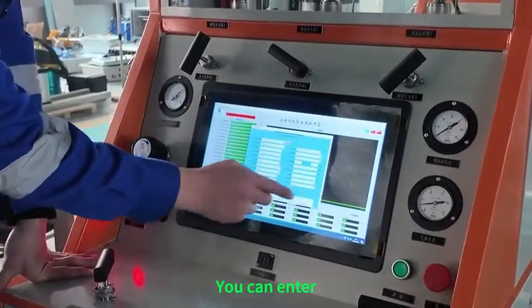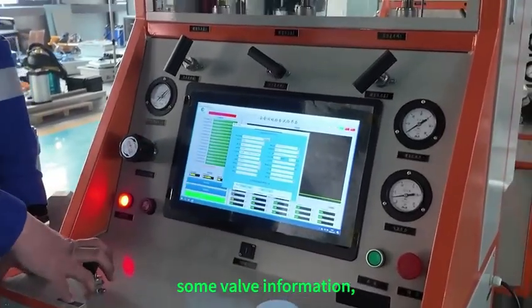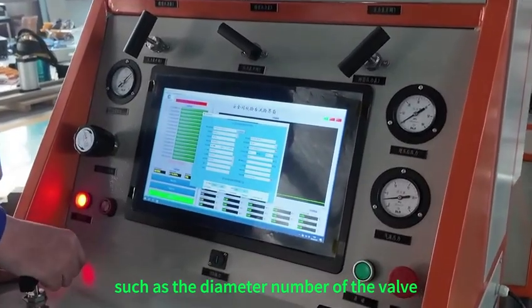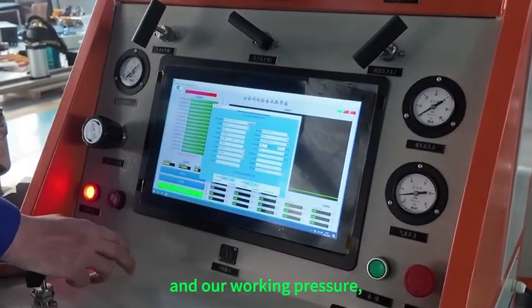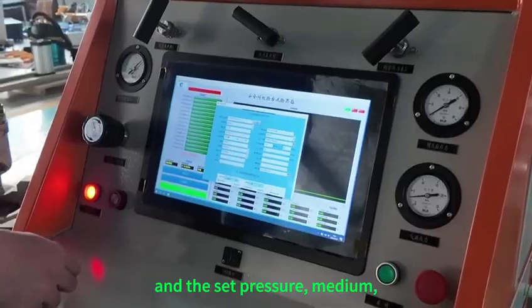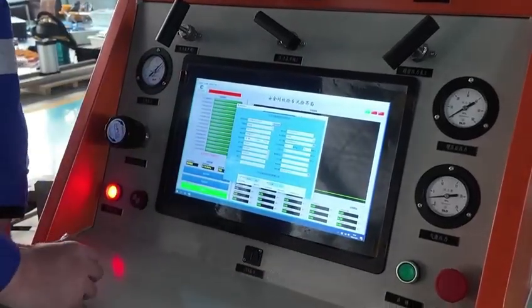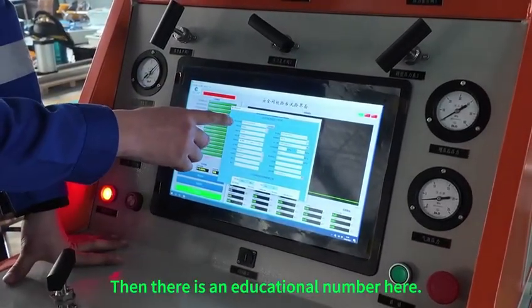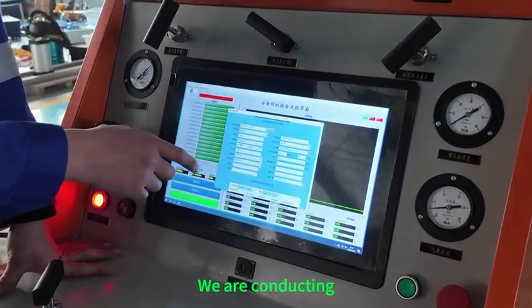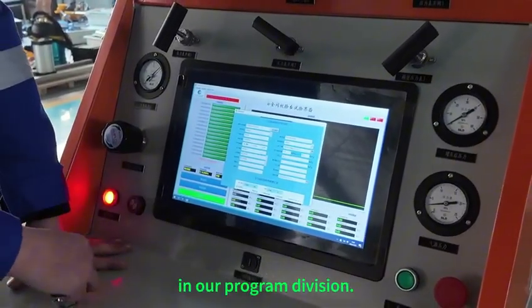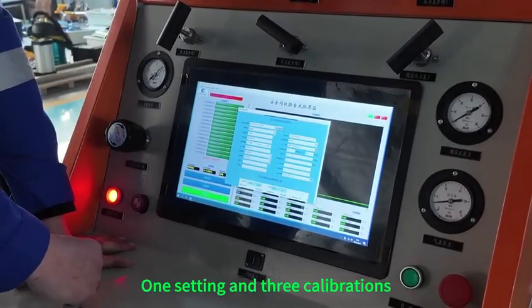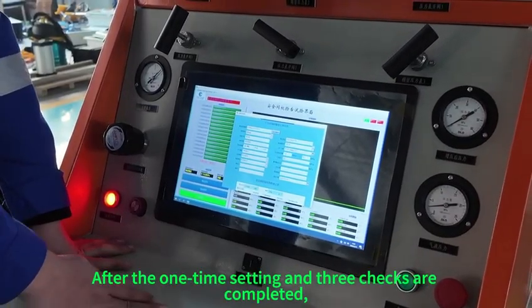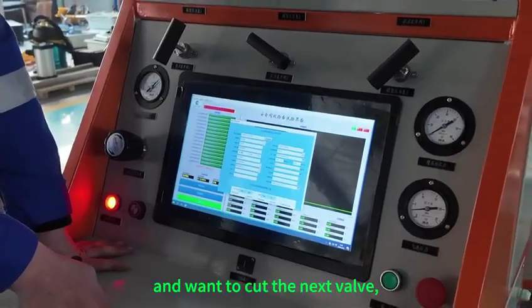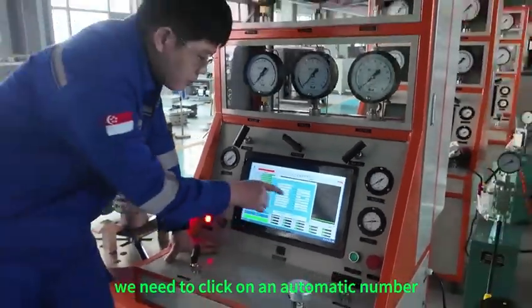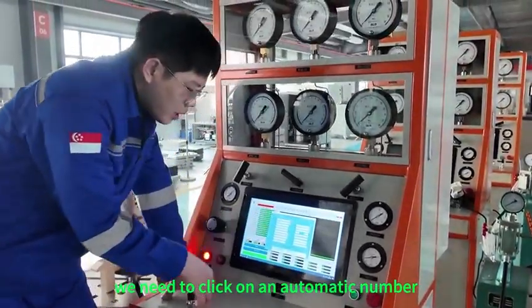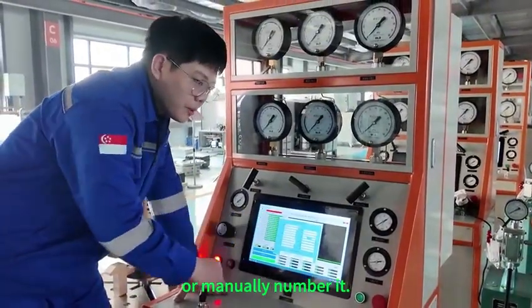You can enter some valve information, such as the diameter number of the valve, our working pressure, the set pressure, and the medium, which can be set here. Then there is a serial number here. In our program, we conduct 1 setting and 3 calibrations. After the 1 setting and 3 checks are completed, if we want to switch to the next valve, we need to click on automatic numbering, or number it manually.